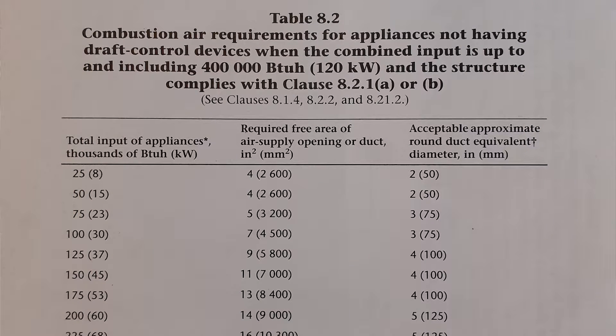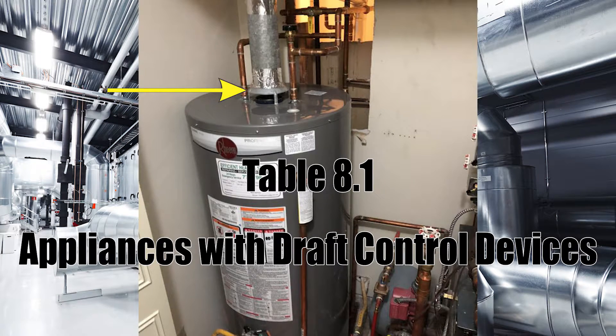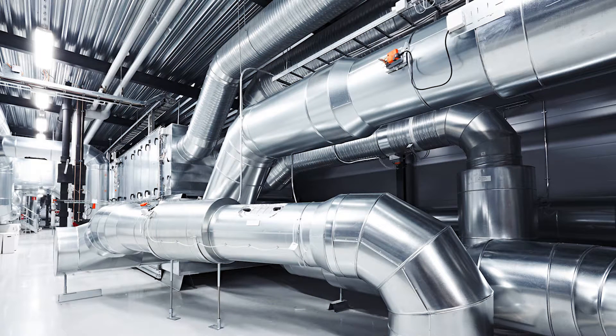Before we get into sizing, let's go through table 8-2: combustion air requirements for appliances not having draft control devices when the combined input is up to and including 400,000 BTUs per hour (120 kilowatts) and the structure complies with clause 8-2-1A or B. The major difference is that table 8-1 is for appliances with draft control devices, while table 8-2 is for fan-assisted appliances. They are different and the number values reflect that.